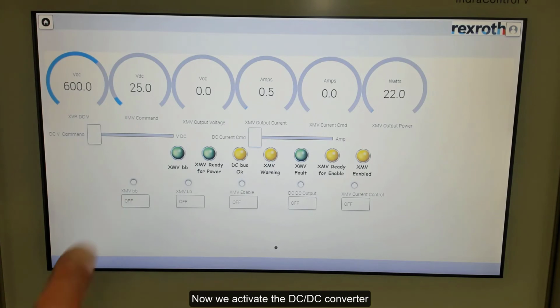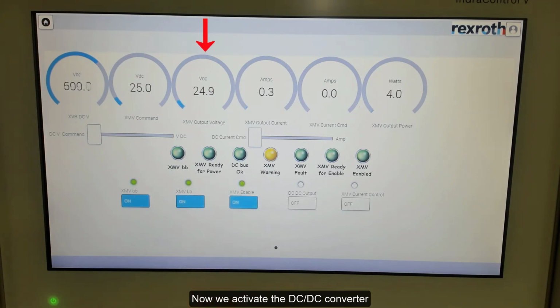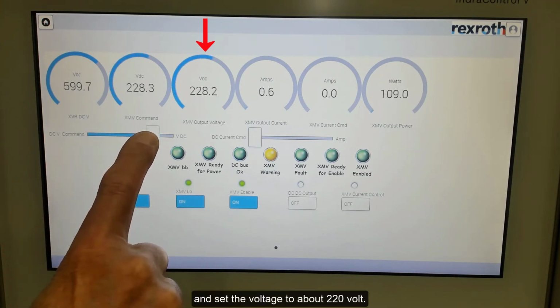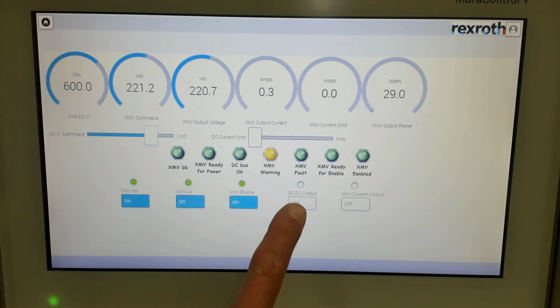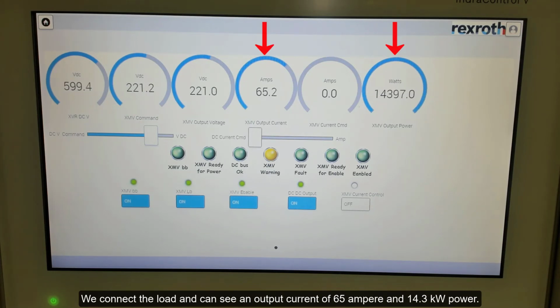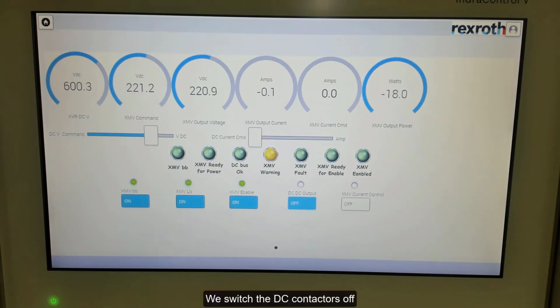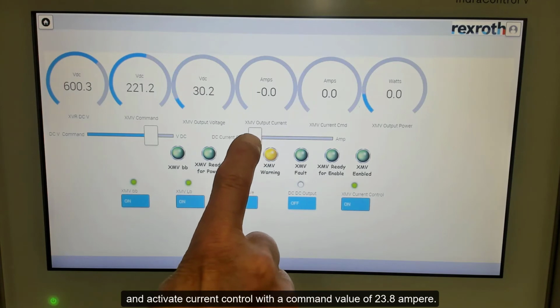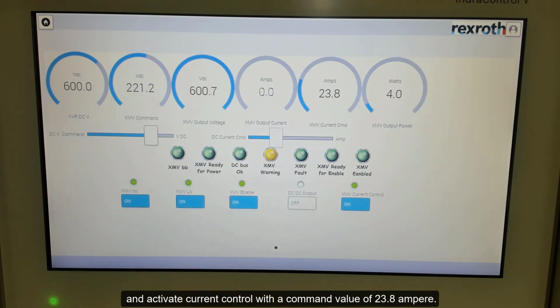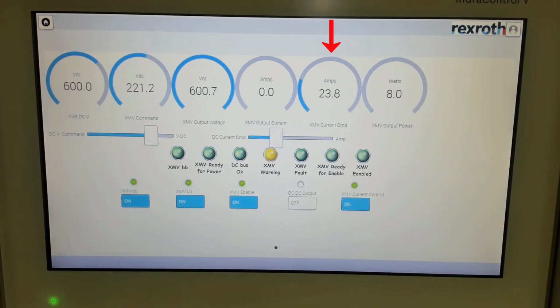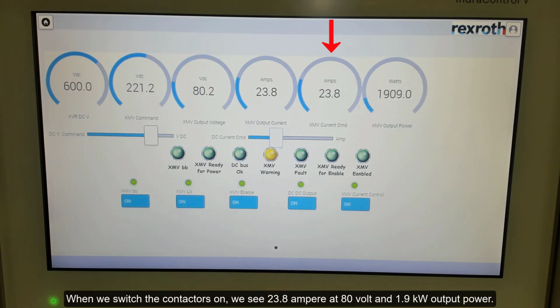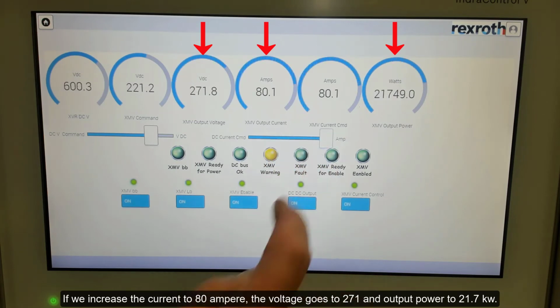Now we activate the DC-DC converter. And set the voltage to about 220 volt. We connect the load and can see an output current of 65 ampere and 14.3 kilowatts power. We switch the DC contactors off and activate current control with a command value of about 23.8 ampere. When we switch the contactors on, we see 23.8 ampere at 80 volt and 1.9 kilowatts output power. If we increase the current to 80 ampere, the voltage goes to 271 and output power to 21.7 kilowatts.